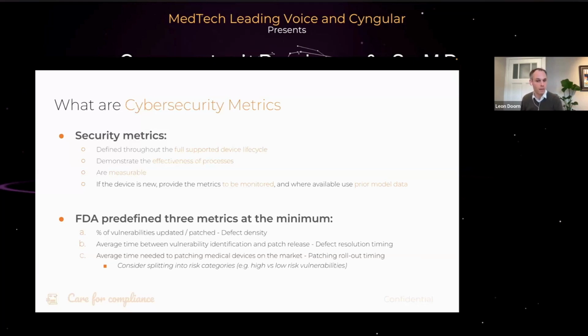Clearly, you should have the cybersecurity metrics throughout the full supported device lifecycle. So when it's on the market, it should demonstrate the effectiveness of your processes and they should be measurable. There are three identified by the FDA that you'll need to do. For example, the percentage of the number of vulnerabilities that have been patched or updated, which I refer to as your defect density. The average time between the vulnerability identification and the patch release, so how long it actually takes you to identify a vulnerability and develop a patch release, which I refer to as your defect resolution timing. And the last one is your patching rollout timing. From the date that you developed the patch, once you installed it at all the sites, how long does that take you?